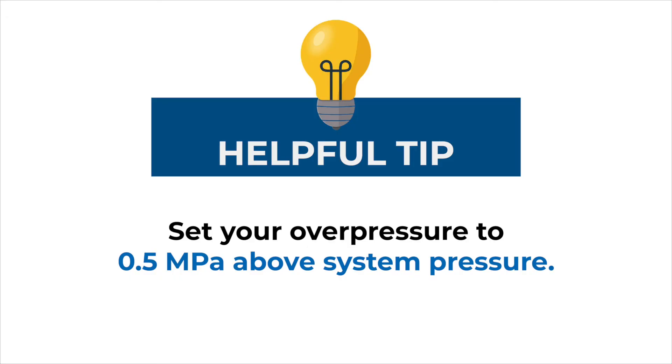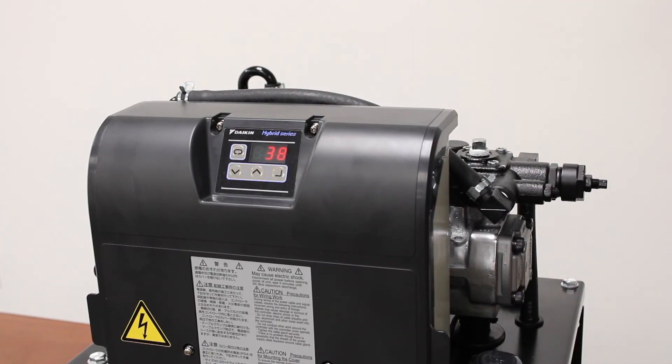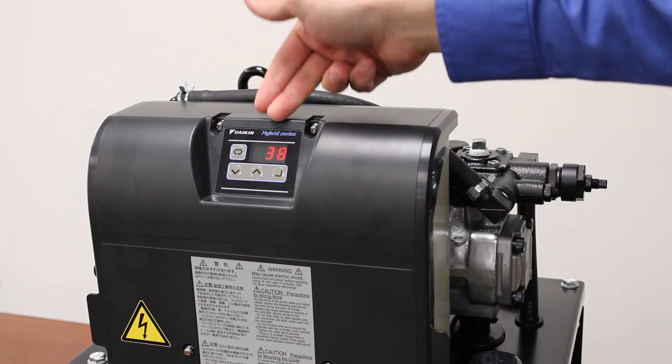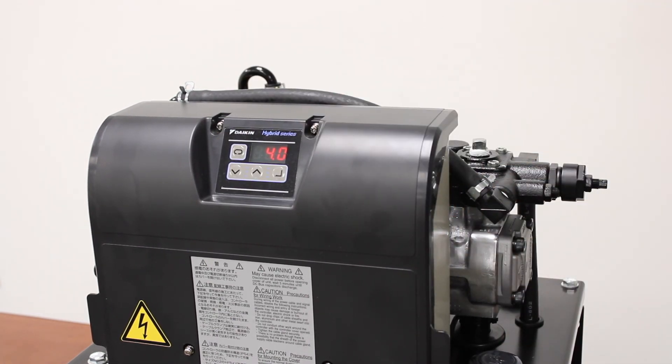Then turn clockwise an additional three quarters of a turn. This sets the over pressure to 0.5 MPa above system pressure. Our over pressure relief is now set and you can tighten down your jam nut. Once we've got everything tight and set, we should be displaying 38. You can go ahead and hit your menu key and it will take you back to display your pressure setting.